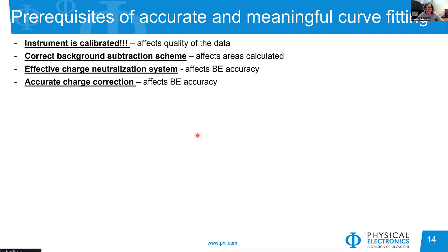Before we start any curve fitting, it all comes back to the quality of the data. We shouldn't underestimate instrument calibration, which affects signal-to-noise, binding energy linearity, etc. Background subtraction is very important — it affects your calculated areas and therefore concentration. If you have samples requiring charge neutralization, you need to ensure it is effective and that charge correction is performed accurately, because these factors affect binding energy accuracy and therefore your identification of chemical moieties.